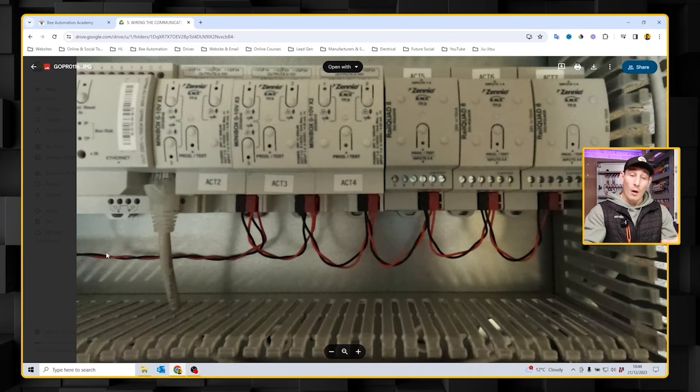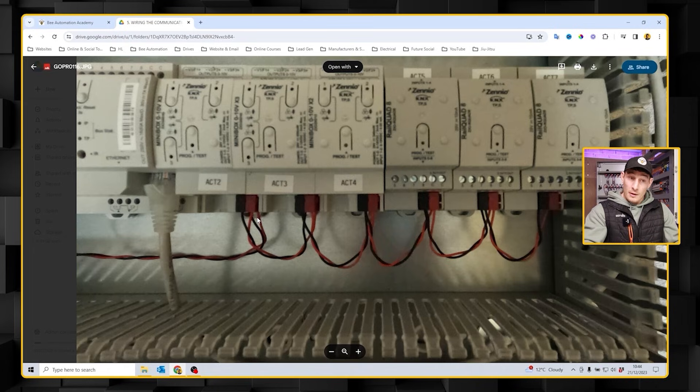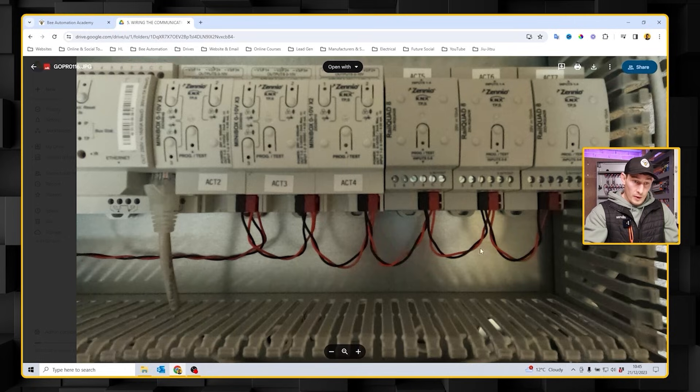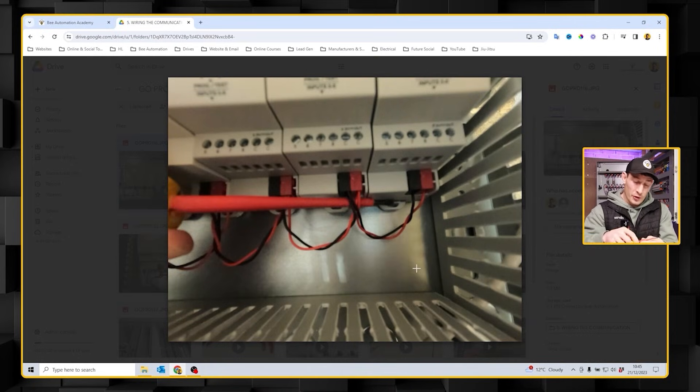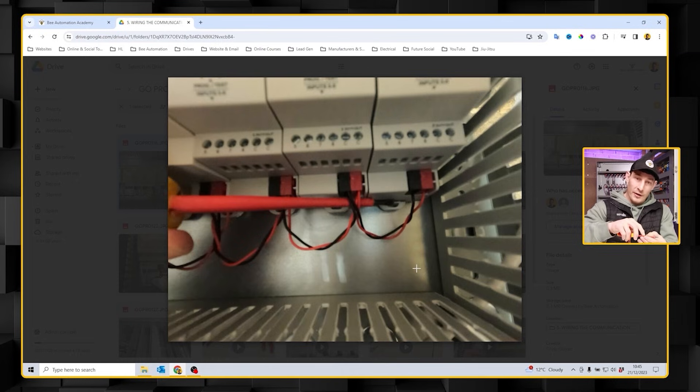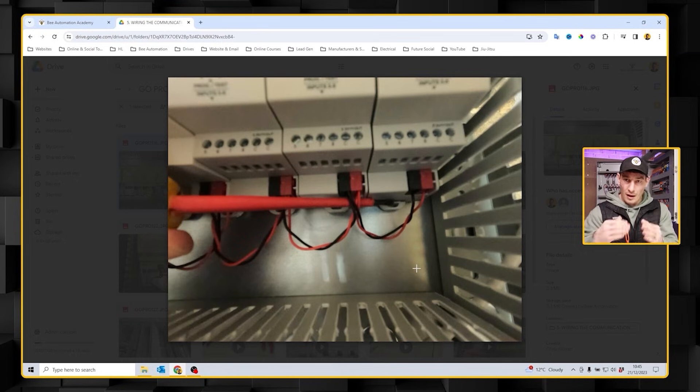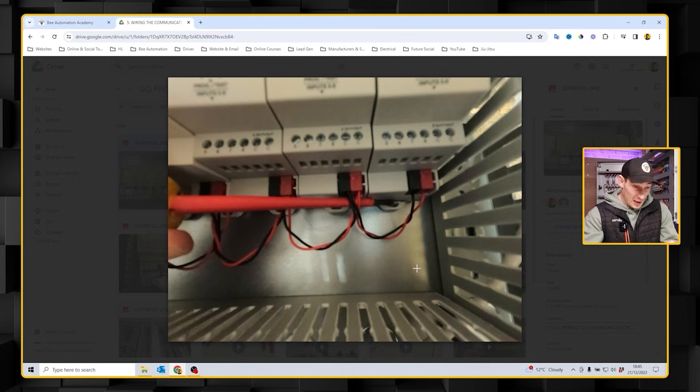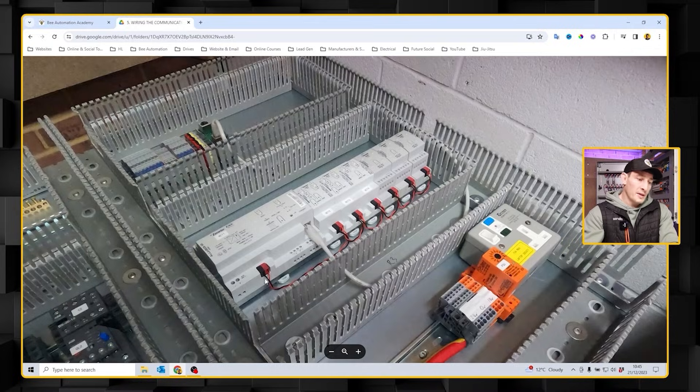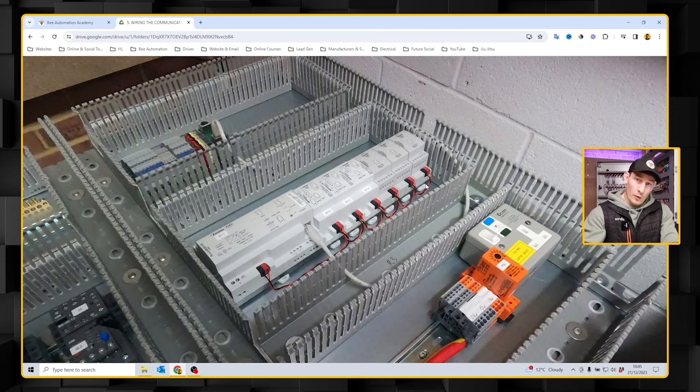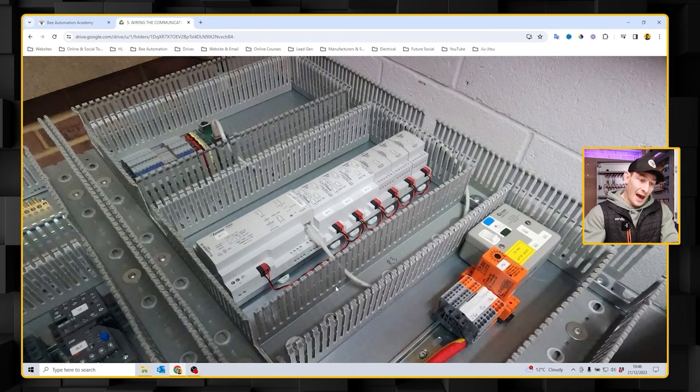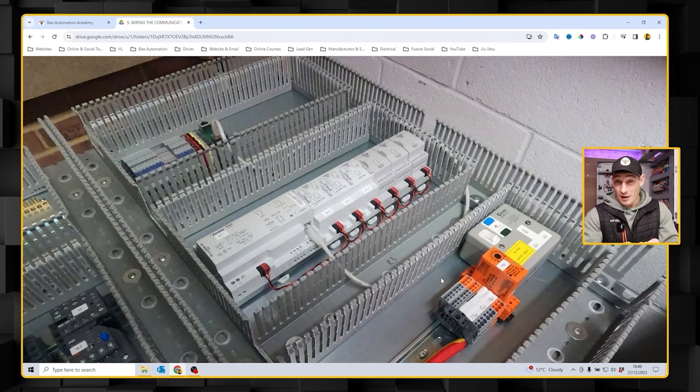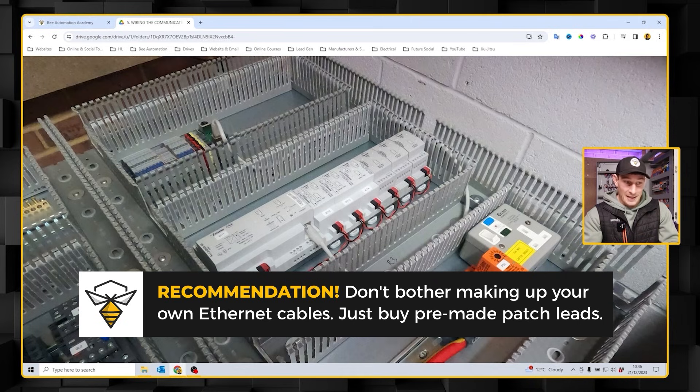First of all, I just do the twisted pair comms and I start on the main controller which is over here and then just bus it across all the modules that are there. This little detail here, you can see I'm actually just using a screwdriver to bend a nice radius on that solid core cable rather than just bending it at a 90 degree angle. It just looks nicer and also keeps the integrity of that solid copper cable.